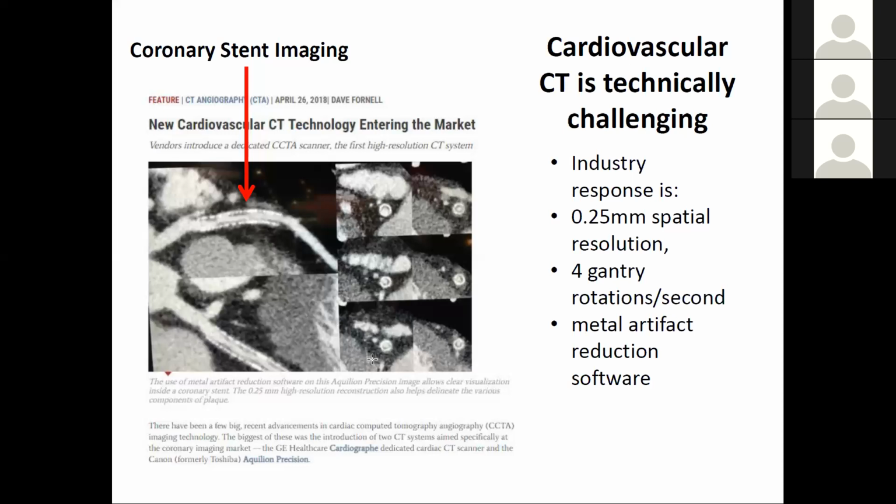See, it's trying to do the residual minimization, and it's fine if it drives it to zero and has a shadow there, okay? So the streaks that you're seeing first, big time, are often because you're still stuck with filter back projection for computational reasons. You don't have enough time to compute the iterative. Sometimes the iterative will start with the filter back projection as the initial guess anyway.